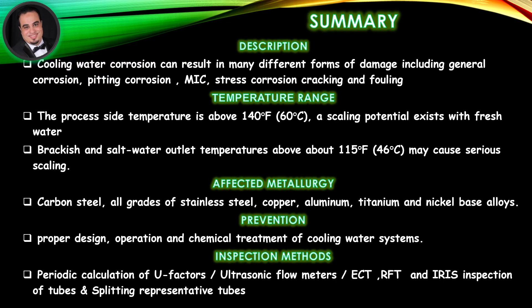Corrosion summary: Cooling water corrosion can result in many different forms of damage, including general corrosion, pitting corrosion, microbiologically induced corrosion, stress corrosion cracking, and fouling. Temperature range: The process side temperature above 140 degrees Fahrenheit creates a scaling potential with fresh water. Brackish and salt water outlet temperatures above about 115 degrees Fahrenheit may cause serious scaling.